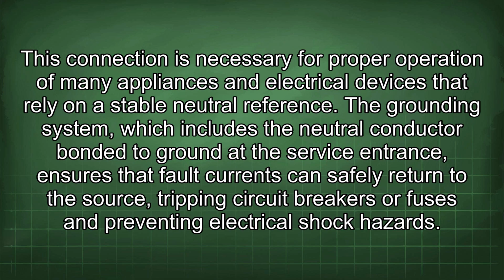This connection is necessary for proper operation of many appliances and electrical devices that rely on a stable neutral reference. The grounding system, which includes the neutral conductor bonded to ground at the service entrance, ensures that fault currents can safely return to the source, tripping circuit breakers or fuses and preventing electrical shock hazards.